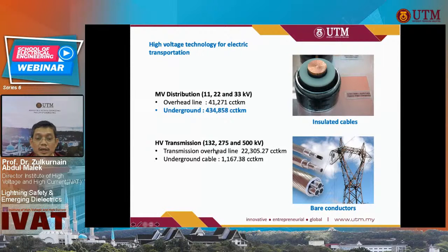Okay, you can say we can protect the line using ground cables at the top. As you can see here, at the top there are ground cables that will protect the phase conductor underneath from being struck by lightning. But more often than not, we still have what we call back flashover, due to voltage generated at the ground wires that flash through the insulator string here into the phase conductor. So lightning can still pose a threat in terms of line outages to our transmission line. Of course, overvoltage in the power cable can also cause damage to insulation.